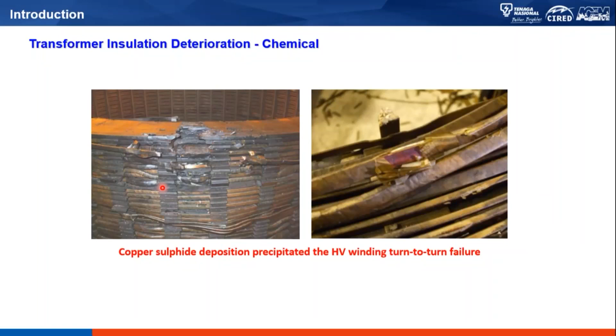If the transformer is not maintained and the acidity is getting higher, this acid will finally cause the insulation to break down, and as part of the byproducts, it would also introduce moisture that could accelerate the formation of this fault in the transformer.